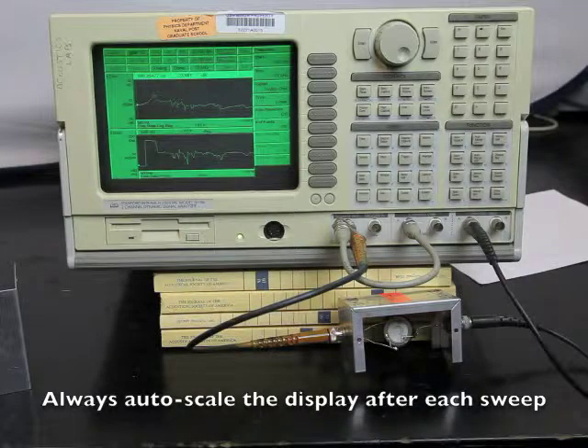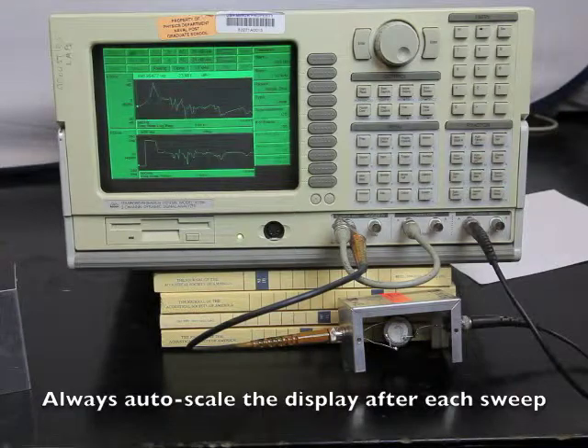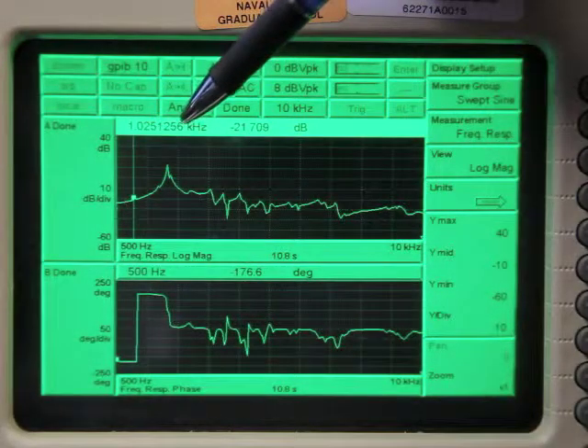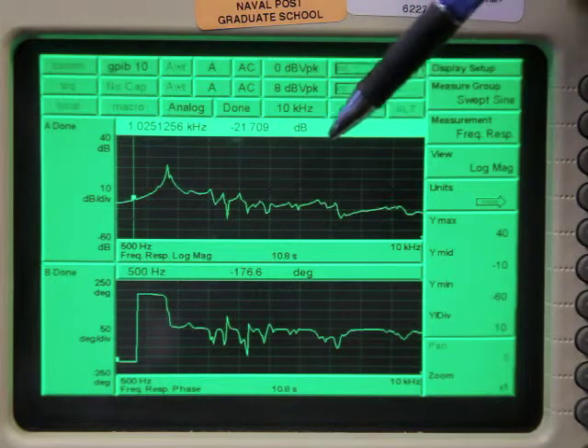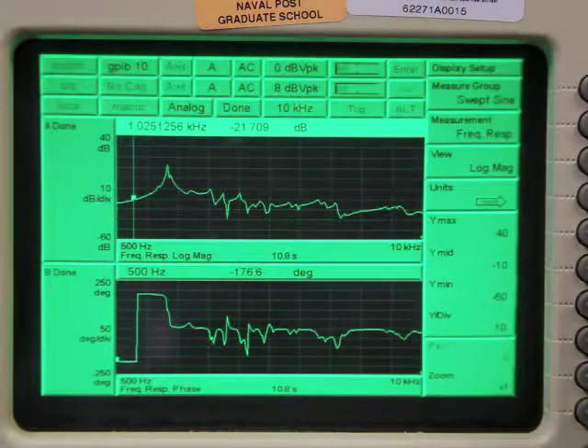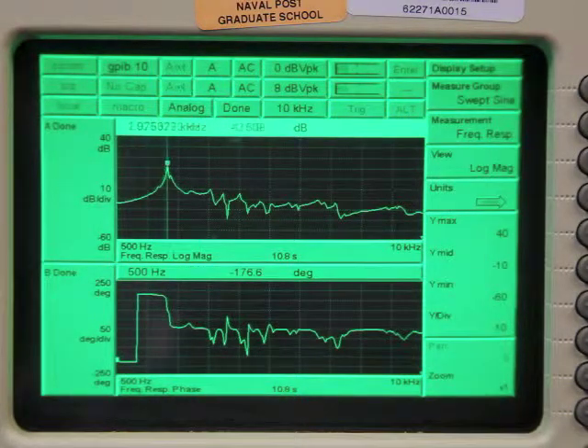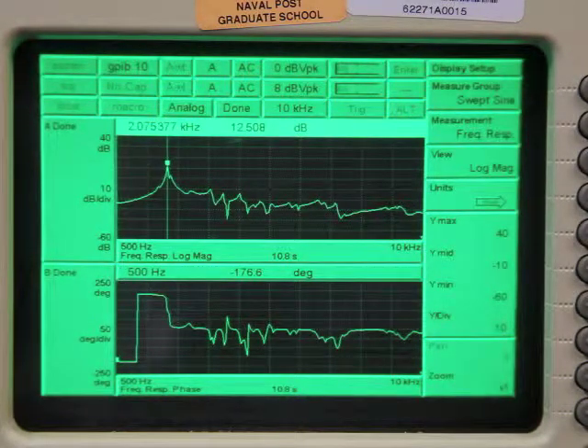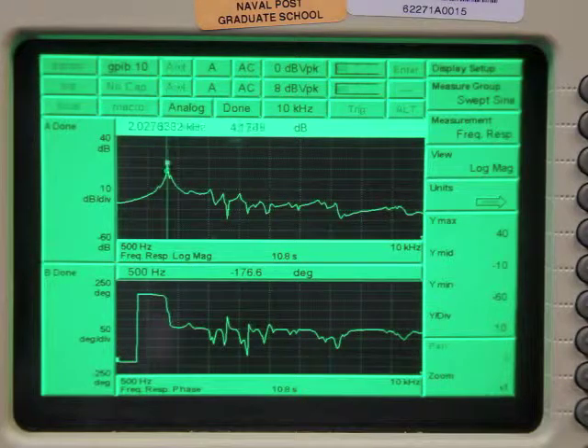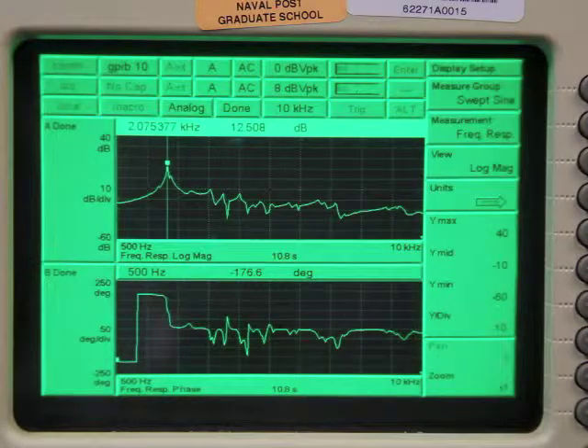You should always get into the habit of doing an auto scale for each channel after you take a new measurement. What we see are a number of resonant peaks and notches that are known as anti-resonances. The most important thing is that first large resonant peak, which is right at 2.075 kilohertz with a magnitude of 12.51 dB.